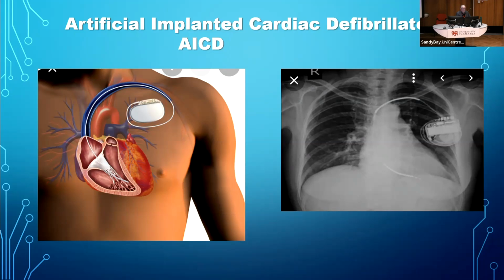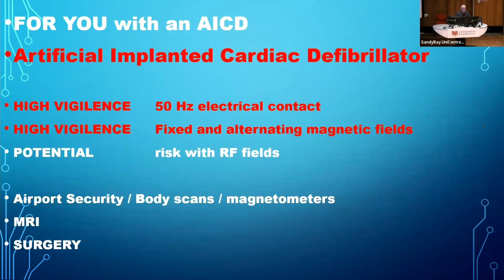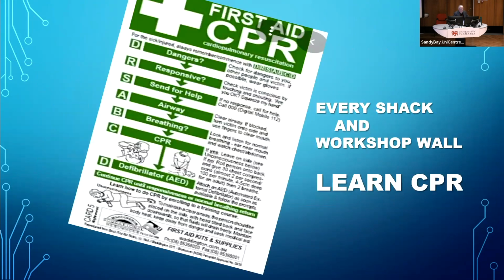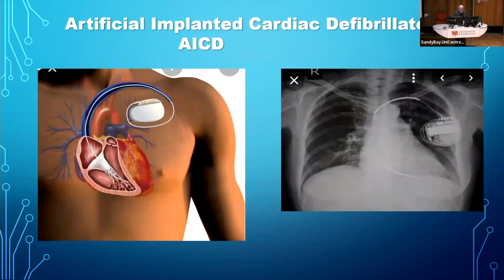This is done deliberately, again, during surgery or some diagnostic procedures where the current can be confused or misinterpreted by the defibrillator as being ventricular fibrillation. Otherwise, it will fire. And that's not a very pleasant experience if you're awake. So if you have an AICD implanted, what does this mean for you? In general, AICDs give you a very wide protection against VF cardiac arrest, but contact with even low amplitude electric currents can potentially cause the defibrillator to fire. What's happened there? Excuse me a moment.